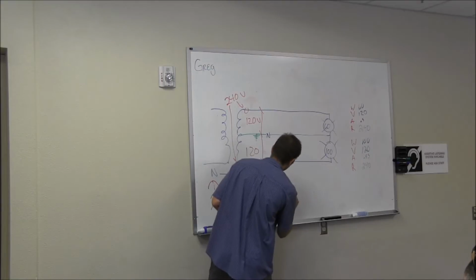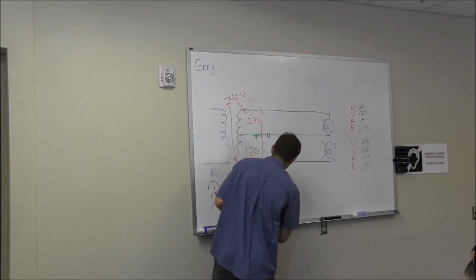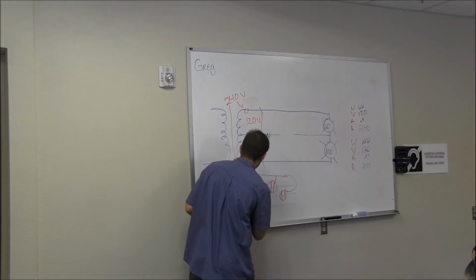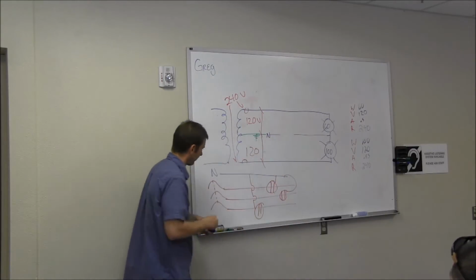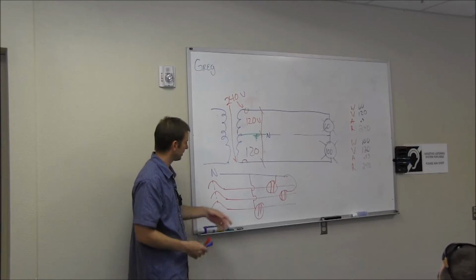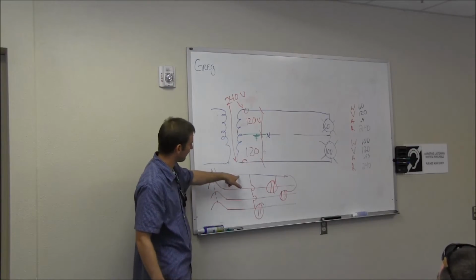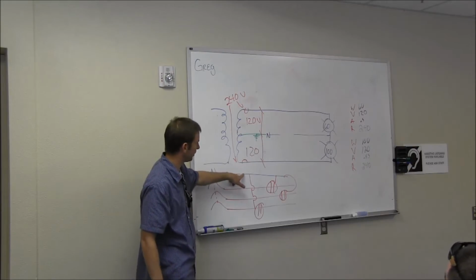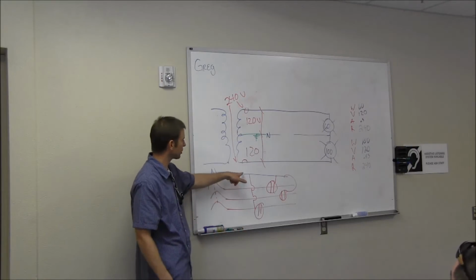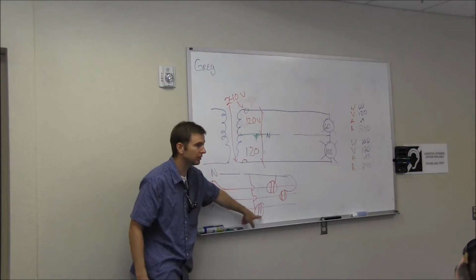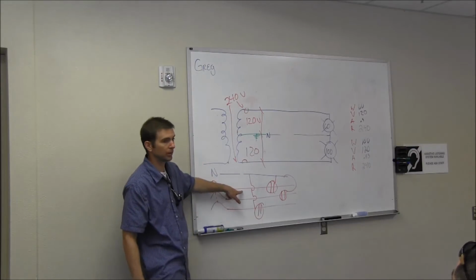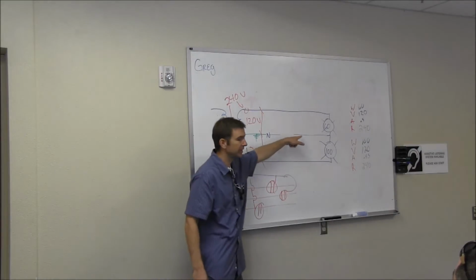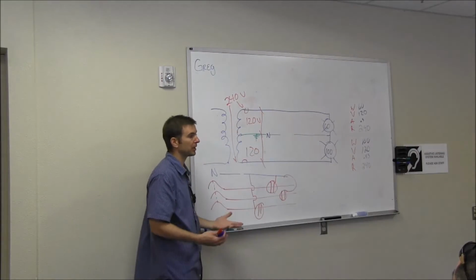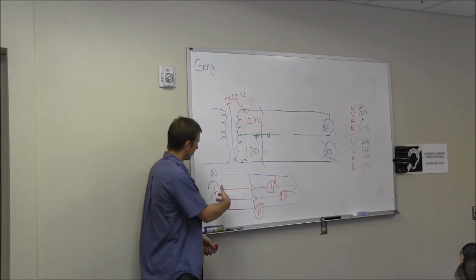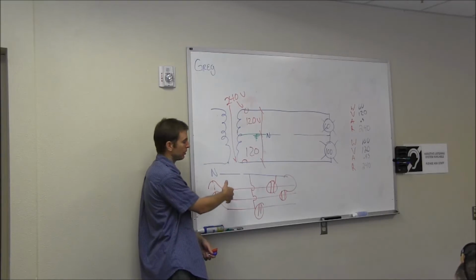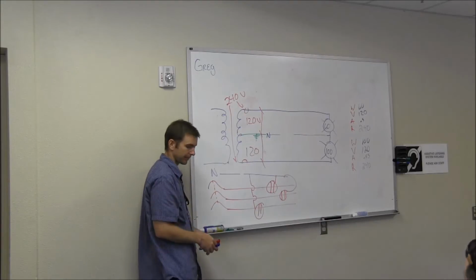And it goes to our neutral, and this one is feeding a receptacle, and it goes to our neutral. If we have 3 different receptacles feeding specialty equipment, and I go to that first receptacle box and open up that neutral because I'm resplicing and repigtailing, I've just opened up that neutral not just for this receptacle, but for this one and this one too. I've created a problem with my receptacles, whatever's plugged in there. So we don't want to do that. We physically tie these together because when we're working on any of these, we have to turn it off.